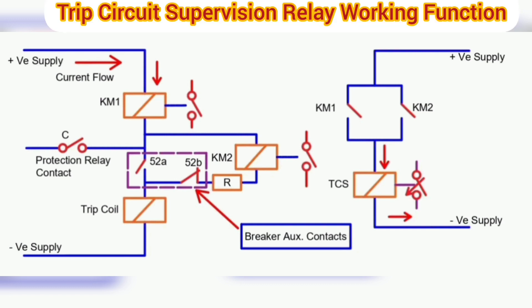The trip circuit supervision relay has three coils: KM1, KM2, and TCS. To limit the current through KM1 and KM2 relay coils, resistance R is added. The relay monitors the healthiness of the trip circuit in both closed and open breaker conditions. The trip circuit supervision function is divided into two categories: 1. Pre-close trip circuit supervision, and 2. Post-close circuit supervision.